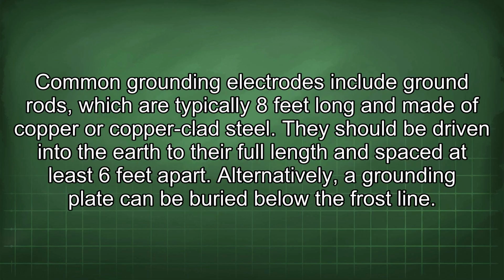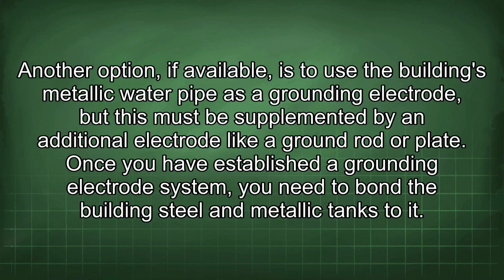Common grounding electrodes include ground rods, which are typically 8 feet long and made of copper or copper-clad steel. They should be driven into the earth to their full length and spaced at least 6 feet apart. Alternatively, a grounding plate can be buried below the frost line. Another option, if available, is to use the building's metallic water pipe as a grounding electrode, but this must be supplemented by an additional electrode like a ground rod or plate.